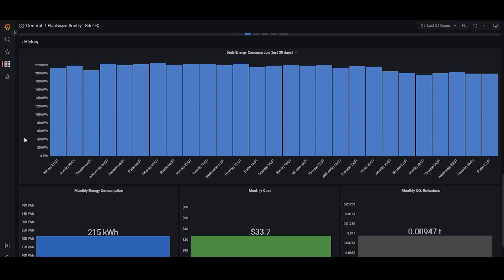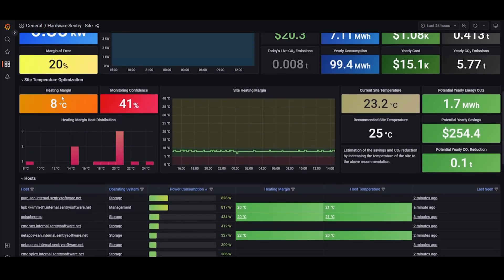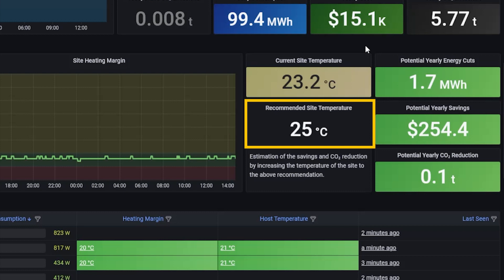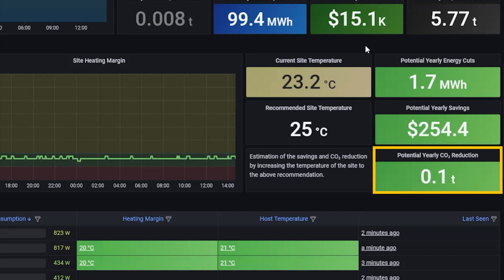And if you're seeing that your site is a big energy consumer and has a large carbon footprint, what you can do is go up to the site temperature optimization section and look at what the recommendation is for increasing the ambient temperature of the data center. In our case here, increasing the ambient temperature to 25 degrees would potentially save us $254 a year and 0.1 tons of CO2 emissions.